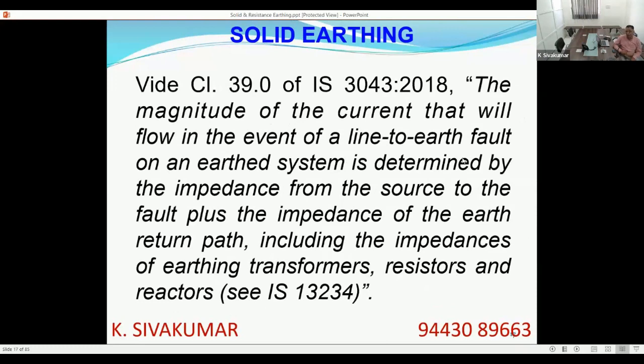Now, what will be the value of this current? In a solidly grounded system, if a single line to earth fault happens, what will be the value of this current? There is a mention in the standard IS 3043, clause 39. The magnitude of the current that will flow in the event of a single line to earth fault on an earthed system is determined by the impedance from the source to the fault plus the impedance of the earth return path. If you opt for transformer earthing, resistance earthing or reactance earthing, any such impedance has to be added. But in solid earthing, these three are neglected: the impedance of the earthing transformer, resistance and reactance. So it is always the fault impedance from the source to the fault plus the earth return path.